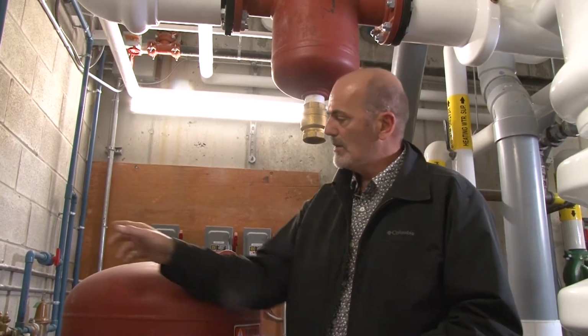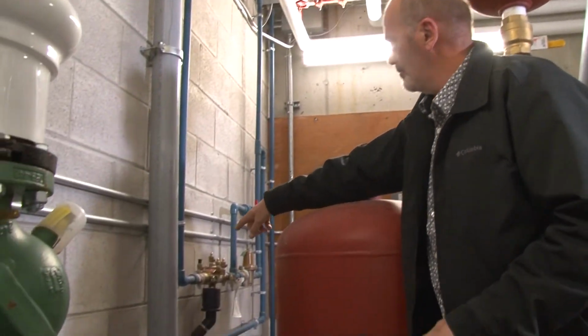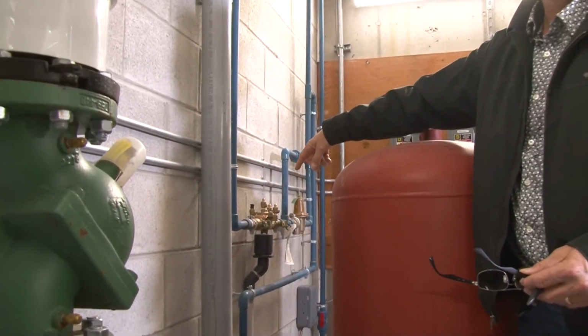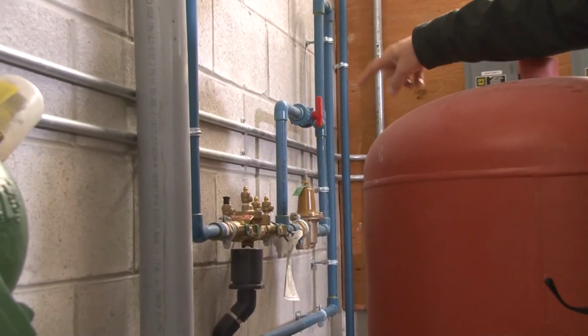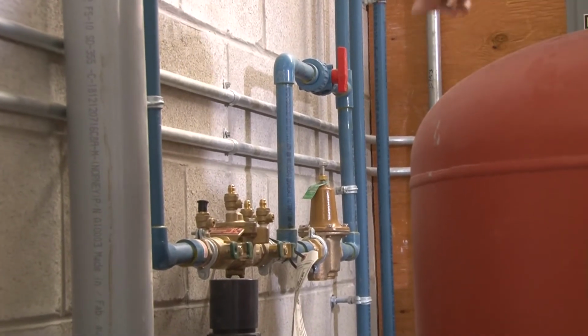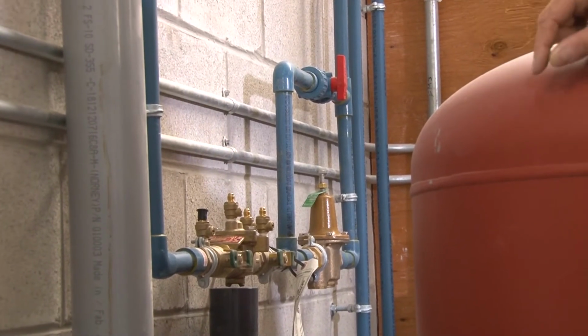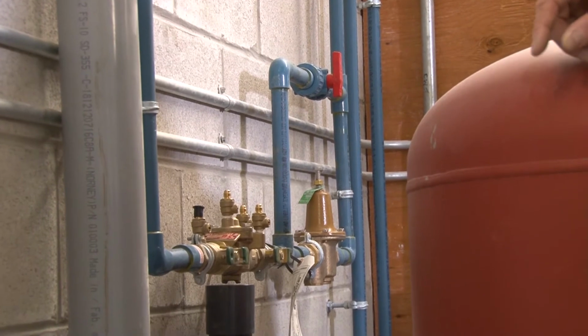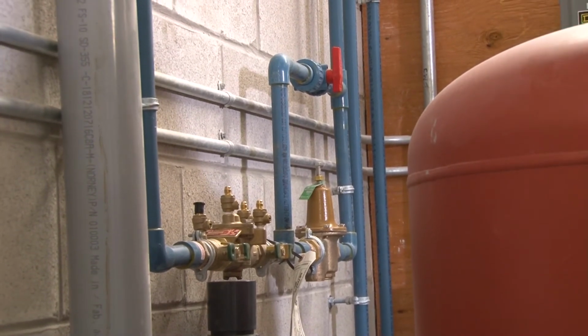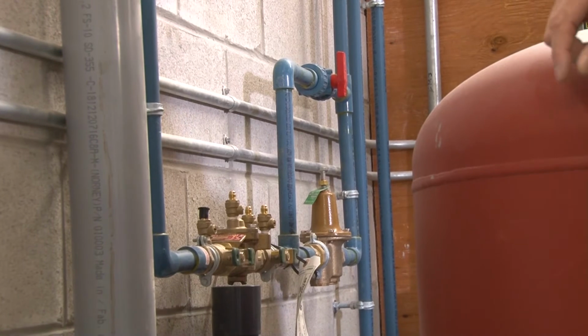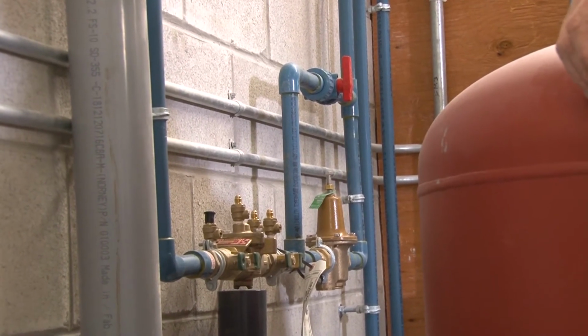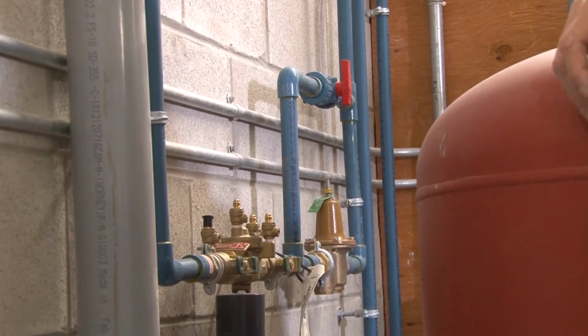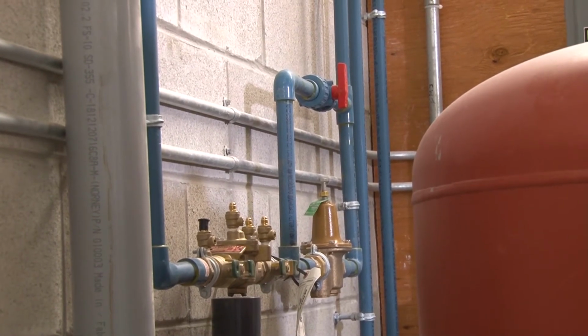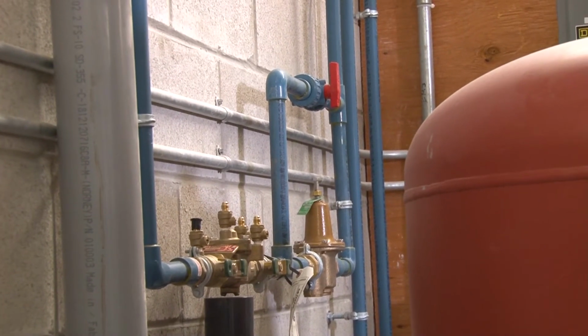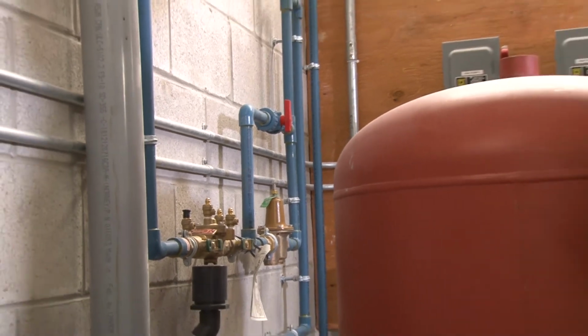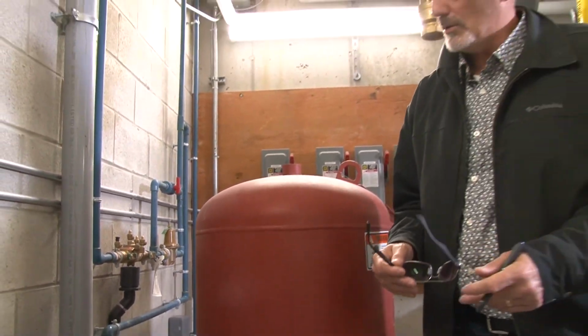Because there is, if you want to focus over here, a pressure reducing fill valve tied to the street water, through a backflow preventer, through the PRV, what will happen is it senses a drop in pressure, that fill valve over there, and as it senses a drop in pressure, it will open up and allow more water into the system to fill this tank and replace that air that's no longer in there because the bladder's ruptured and it's been pushed out in the system and removed by the air eliminating equipment.